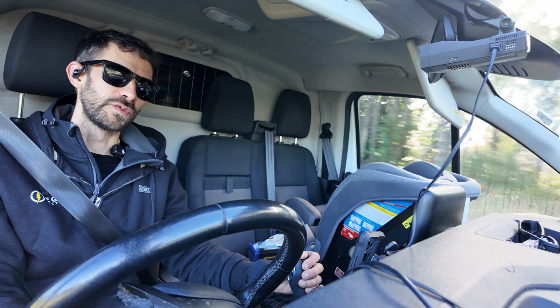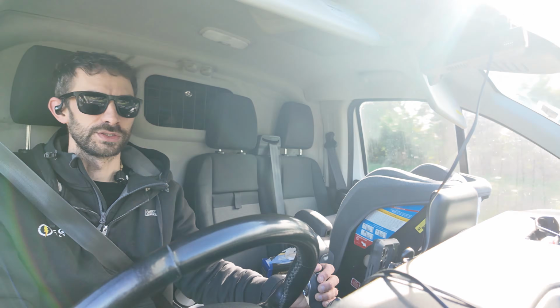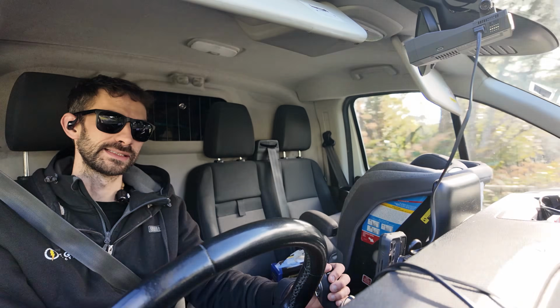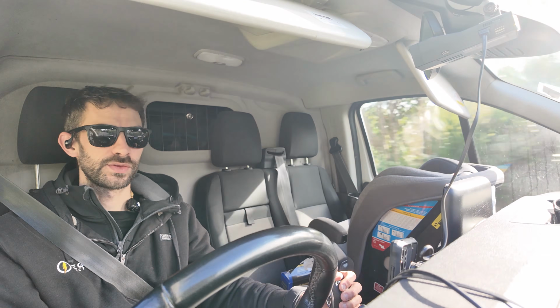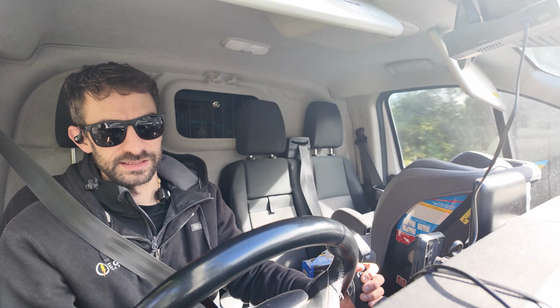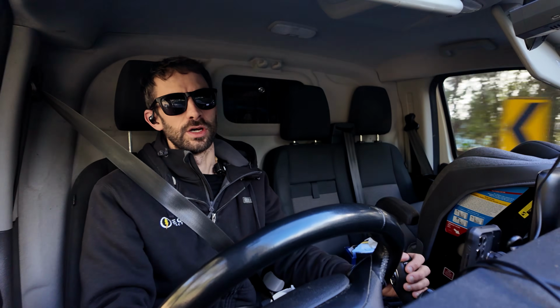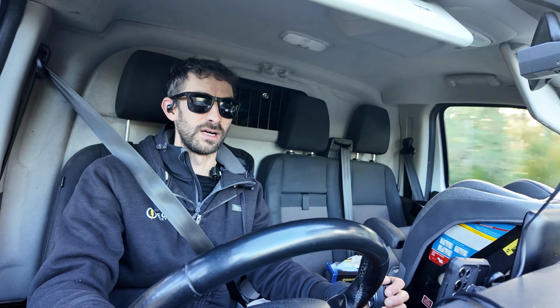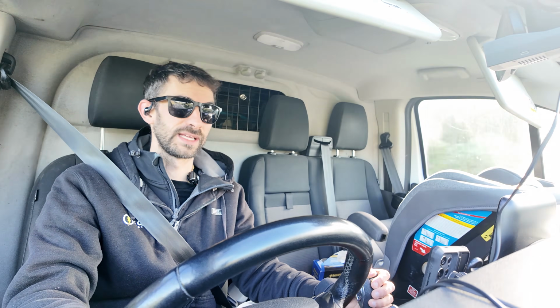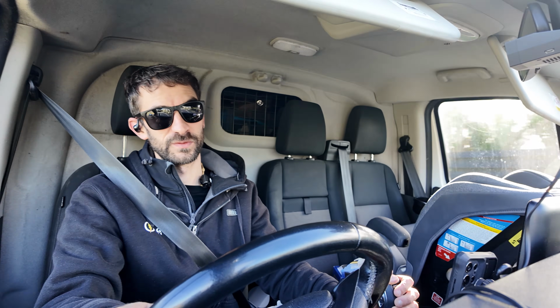Other things you need two faults. For example, you need your circuit protection to fail and you need to have a fault to earth, but there's just no protection against it. So like I said before, the TT system with an RCD would protect against it. But yeah, finishing off the point about what does the earth electrode actually do? So how rusty is it before it fails? No one can tell you.